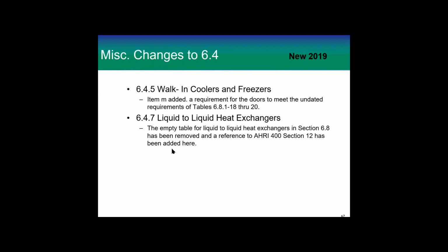All right. So miscellaneous changes to 6.4. So this is again, 6.4 is mandatory requirements. Walk-in coolers and freezers. There's a changed requirement for the doors to meet updated requirements. And then liquid to liquid heat exchangers. We've carried this empty table for liquid to liquid heat exchangers, section 6.8, and we've just removed it, and we've referenced AHRI 400, which is some requirements for liquid heat exchangers. There was not a good way for us to build a table that we were happy with, ever get a consensus table. So, and then I'll talk a little bit about walk-in coolers and freezers.